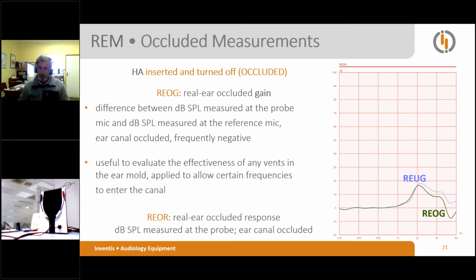Inserted and turned off. So, occluded measurement. The hearing care professional then inserts the hearing aid into the patient's ear canal. Pay attention to minimizing the possible displacement of the probe tube. In occluded mode, occlusion response, real ear occluded response, or occluded gain, real ear occluded gain, REOG, measurement can be taken with the hearing aid inserted but turned off in order to establish the level of occlusion introduced by the physical presence of the hearing aid.